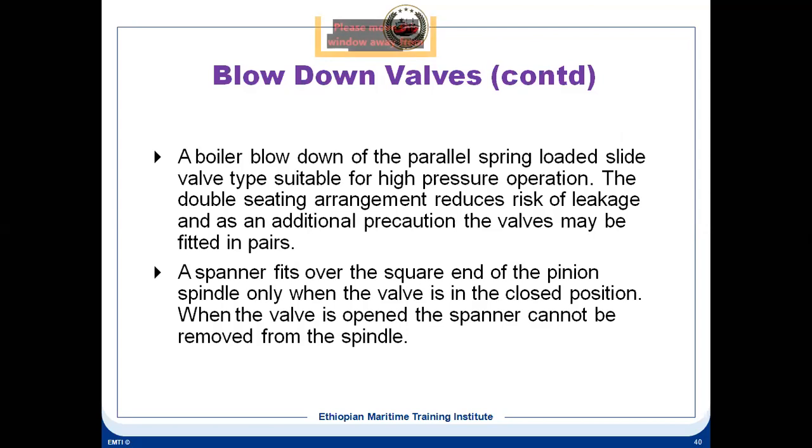A blowdown valve of the parallel spring-loaded slide valve type. Basically, they are talking about a gate valve type of blowdown, which is again spring-loaded and suitable for high pressure operation. Basically, the gate valve has got a double seating arrangement, so that reduces the risk of leakage. And as an additional precaution, the valves may be fitted in pairs.